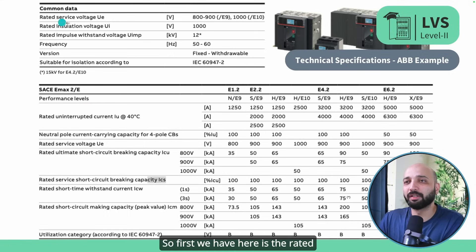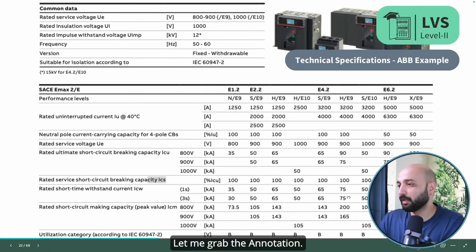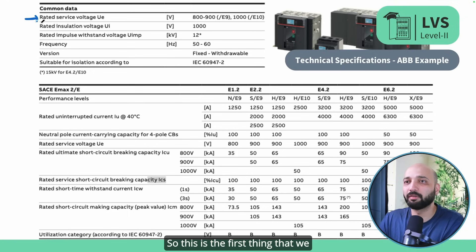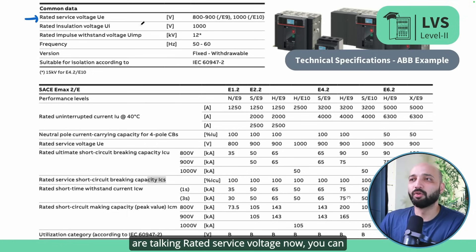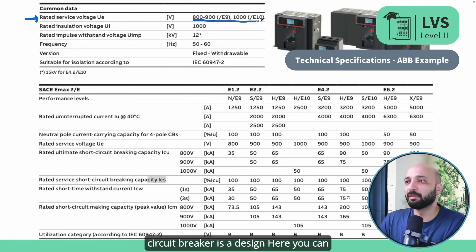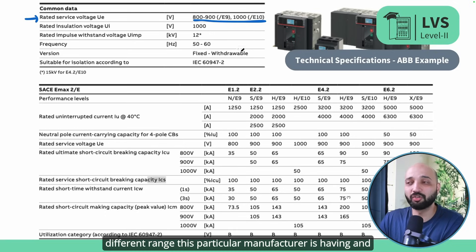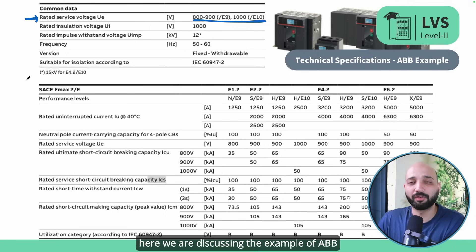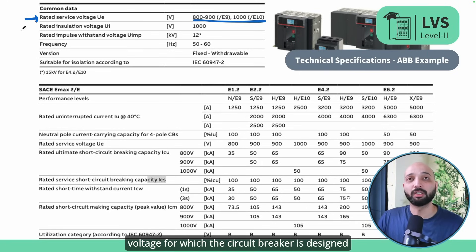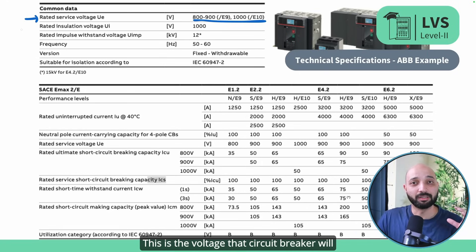The first parameter is the rated service voltage, Ue. This is the voltage for which the circuit breaker is designed. Here you can see it is mentioned as 800 volts, 900 volts, or 1000 volts — these are the different ranges this particular manufacturer offers. We are discussing the example of an ABB circuit breaker. This is the voltage that the circuit breaker will carry without any problem.